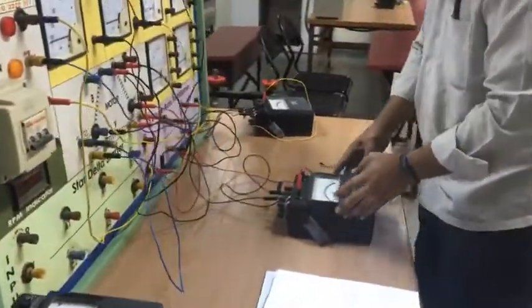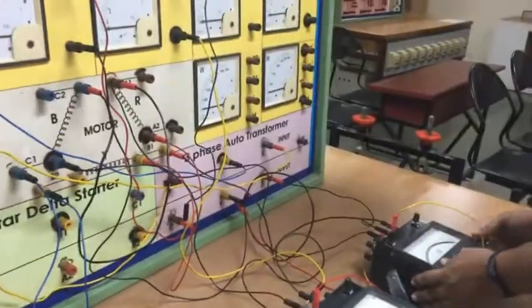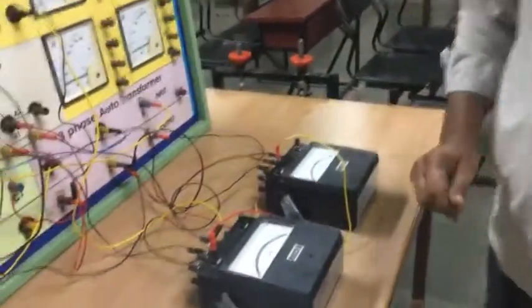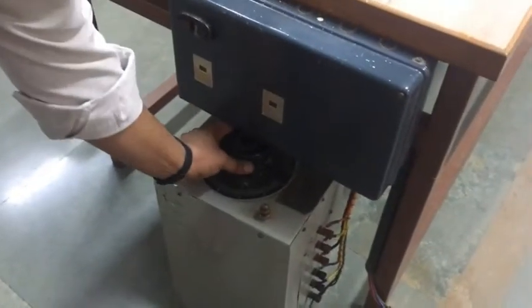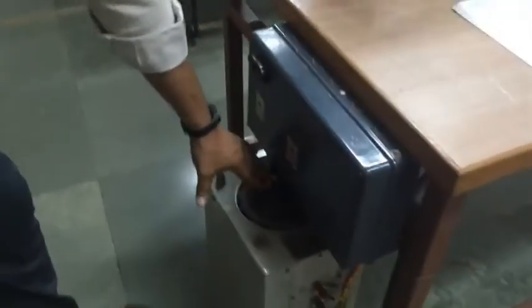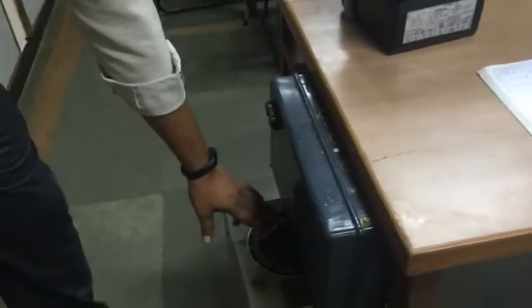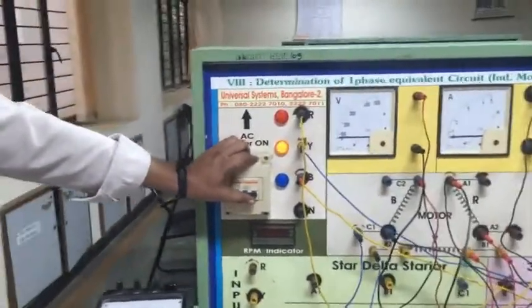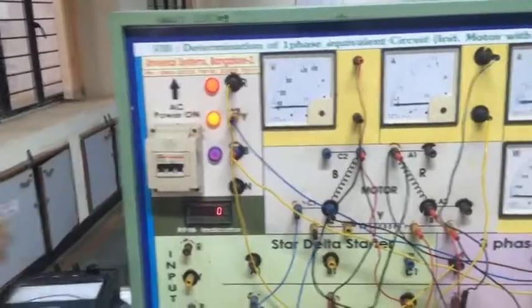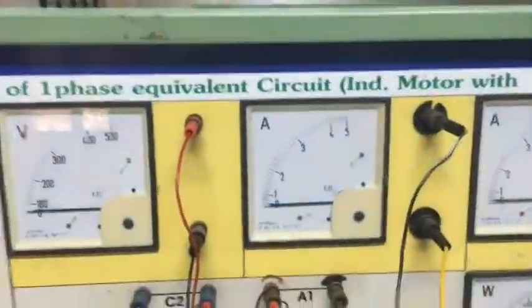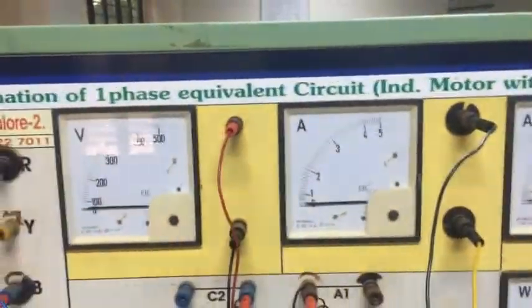Now after connecting the two UPF wattmeters, please check whether the auto transformer is in minimum position. If it is not, please bring the auto transformer to minimum position. Once it is in minimum position, switch on the three-phase mains. Now slowly vary the auto transformer and apply the rated current, not the rated voltage. Apply the rated current of 4.8 amps.